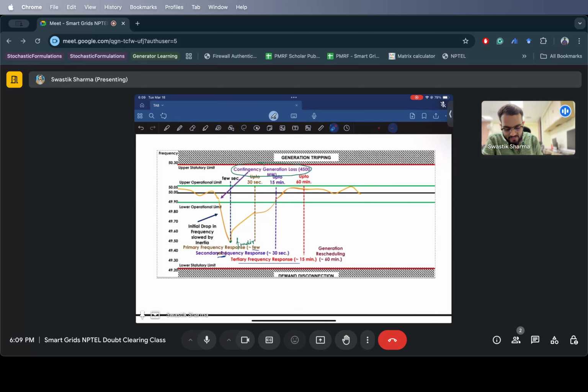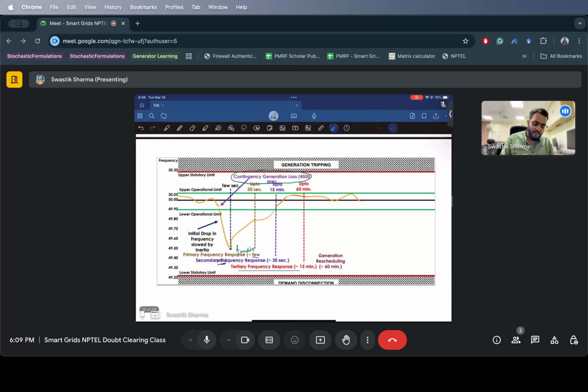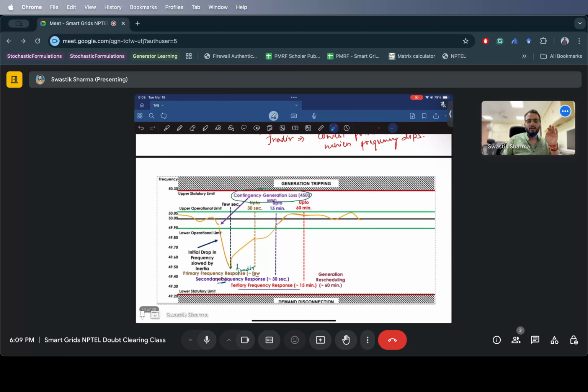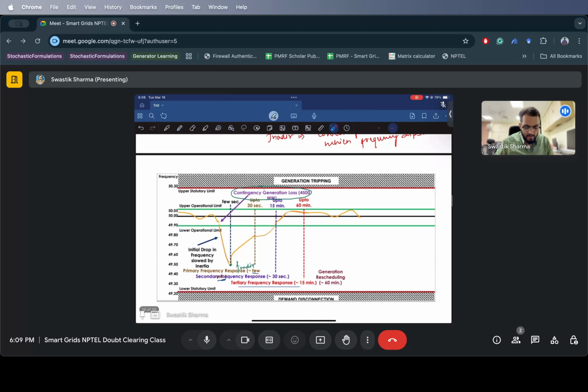You have an upper statutory limit and a lower statutory limit. If the frequency increases beyond this, your generators are tripped, and if the frequency dips beyond this, your demand is disconnected. So you can have brownouts. This is how frequency is controlled in India. This is some case study that I got from the internet.